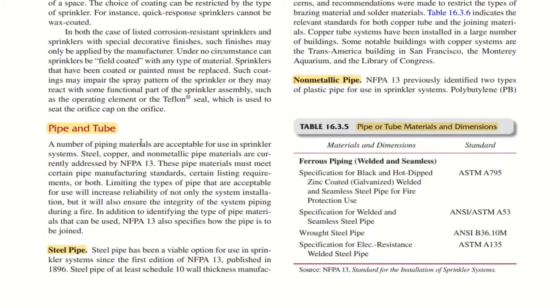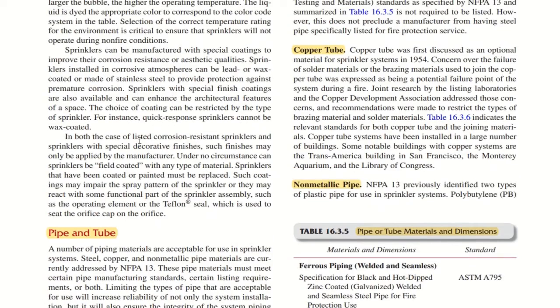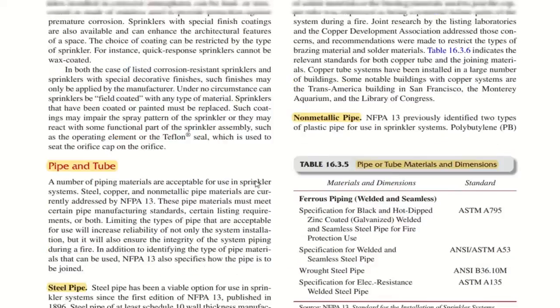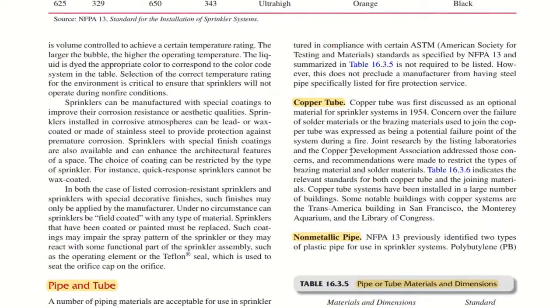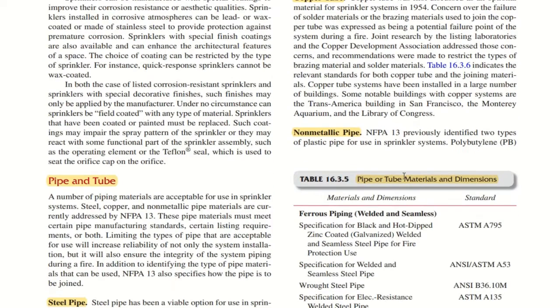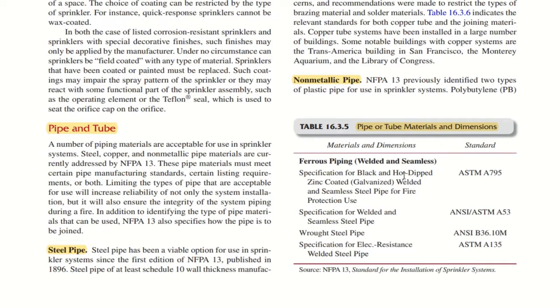Pipe and tubes: system components are also covered here, like steel pipes. Copper tube can also be used, and non-metallic pipes can also be used, but you can check NFPA 13, which is the standard for installation of sprinkler systems. Here, in table 16.3.5 in the Fire Protection Handbook, pipe or tube materials and dimensions are mentioned, and the standards that can be used for our sprinkler system are shown here. So you have the specification for welded and seamless steel pipe.